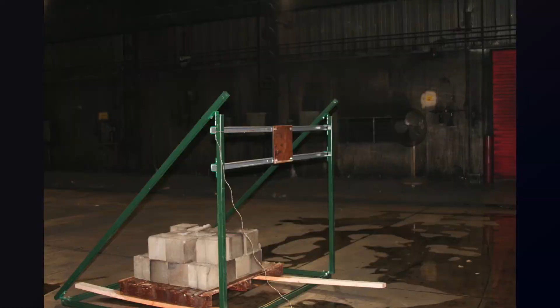What we found was that with a smoothbore, 1-inch nozzle at 21 psi nozzle pressure, when 1,000 volts was on that plate, 5.7 milliamps was detected back at the coupling. When we went below 600 volts, that amount of current was lower than the perceptible level.